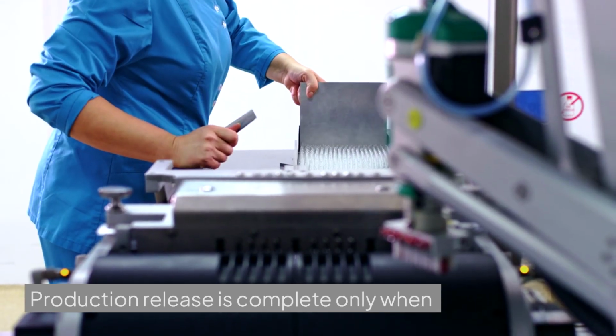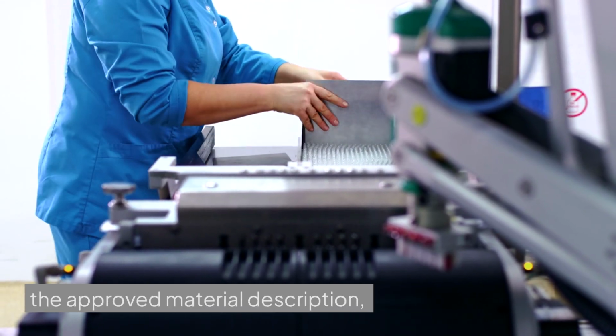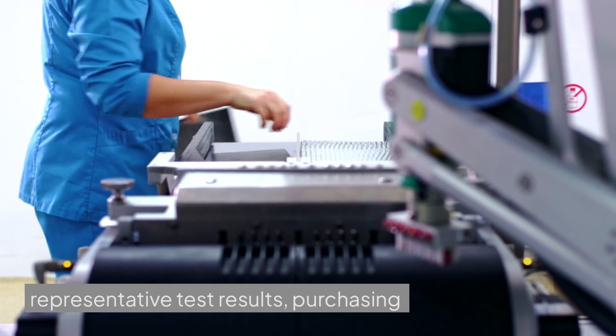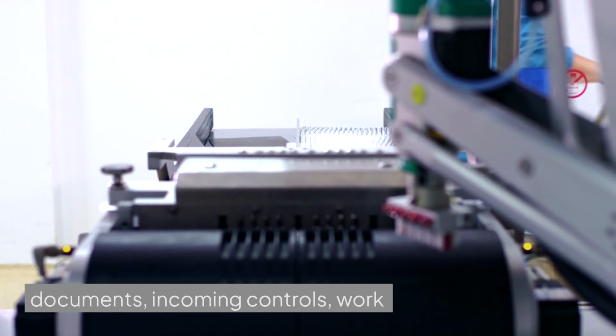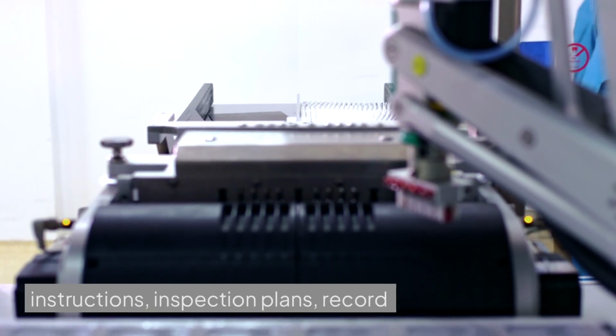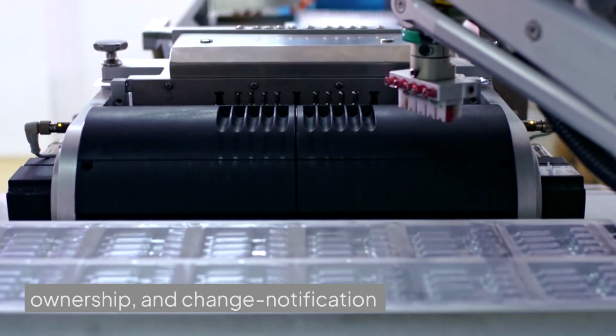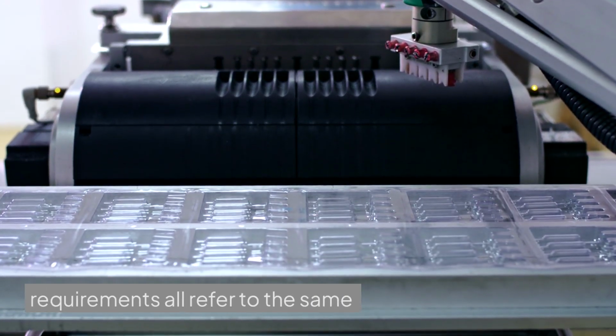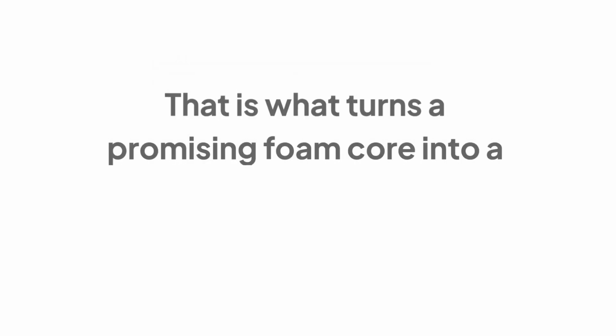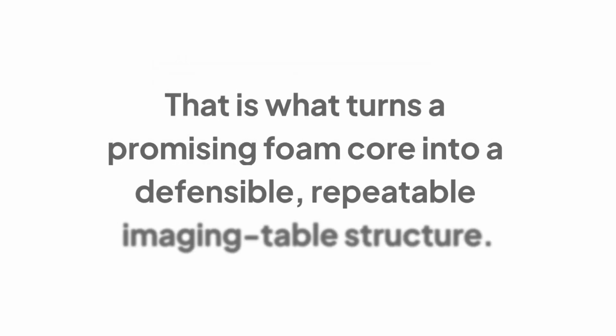Production release is complete only when the approved material description, representative test results, purchasing documents, incoming controls, work instructions, inspection plans, record ownership, and change notification requirements all refer to the same control design. That is what turns a promising foam core into a defensible, repeatable imaging table structure.